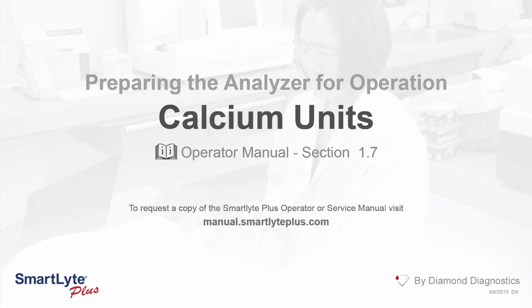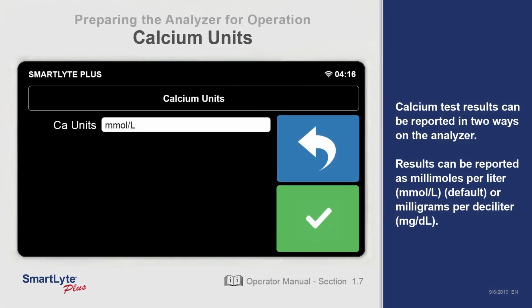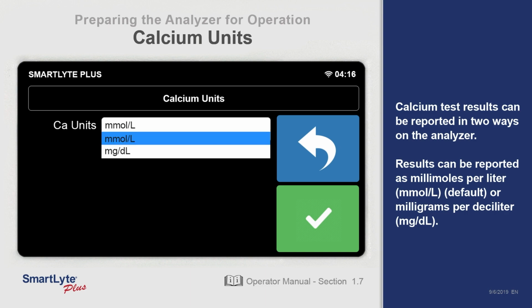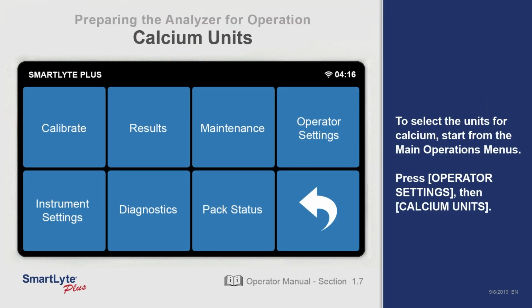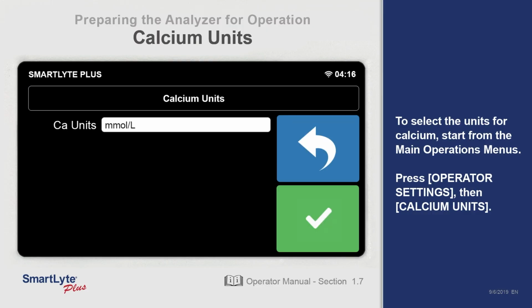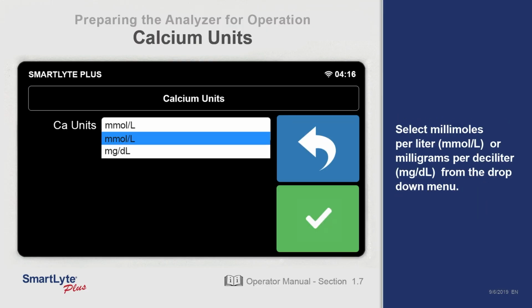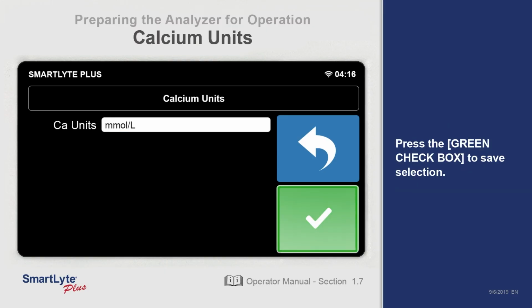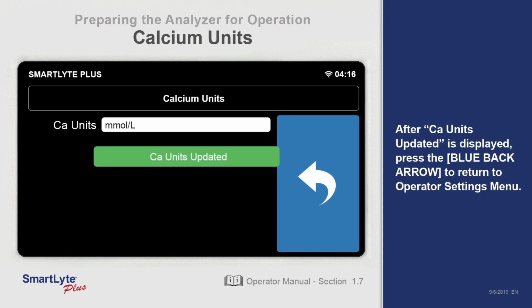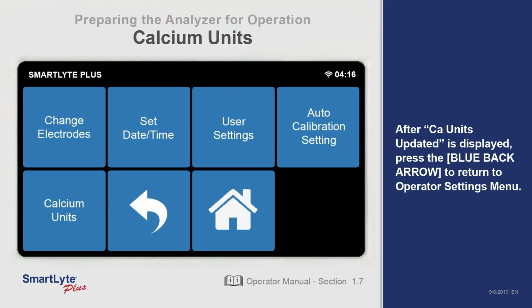Selecting the calcium units on the SmartLyte Plus. Calcium test results can be reported in two ways on the analyzer. Results can be reported as millimoles per liter or milligrams per deciliter. To select the unit for calcium, start from the main operations menu. Press Operator Settings, then Calcium Units. Select millimoles per liter or milligrams per deciliter from the drop-down menu. Press the green checkbox to save the selection. After the calcium units updated is displayed, press the blue back arrow to return to the Operator Settings menu.